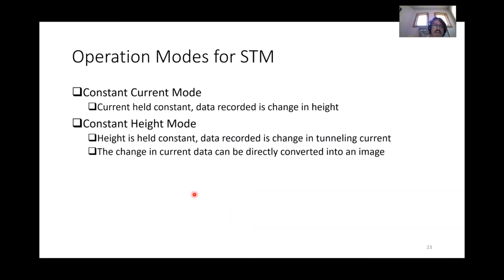Operation modes for scanning tunneling microscope. So constant current mode, the current is held constant, and data is recorded as a change in height. And so here, the data is driven by the piezoelectric device, basically, that we talked about before. Constant height mode, the height is held constant and the current is different, okay? Or the current changes, and the measurement is the change in tunneling current.